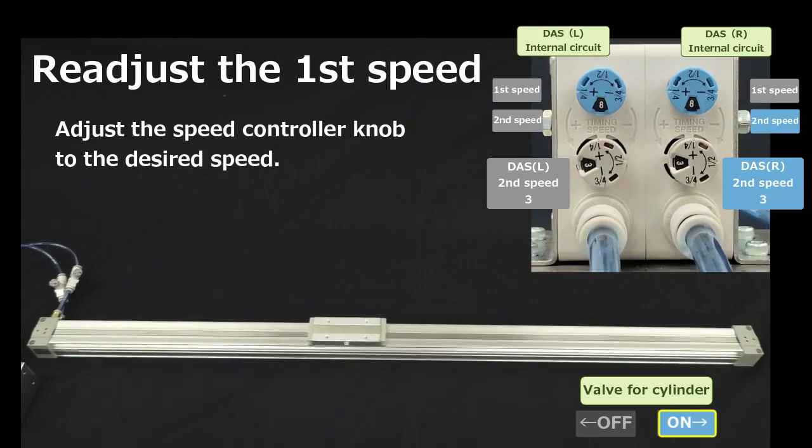Here, the speed controller is fully opened in a single adjustment. If the cylinder collides with the stroke end, adjust the knob of the speed controller in the negative direction to lower the first speed.